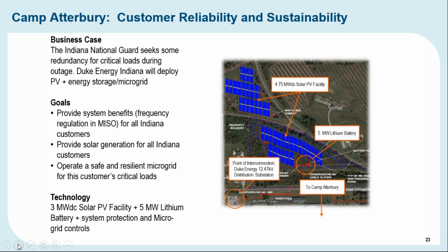Going into some of the technical issues — on the islanding piece, we found that the solar and battery technology works well. Where we've run into challenges is that our grid isn't really based around inverter-based microgrids. It's based around rotational equipment and the protections and control schemes that go with that.